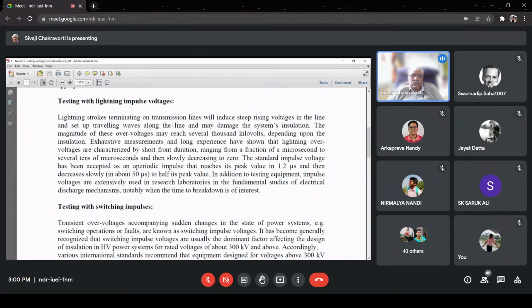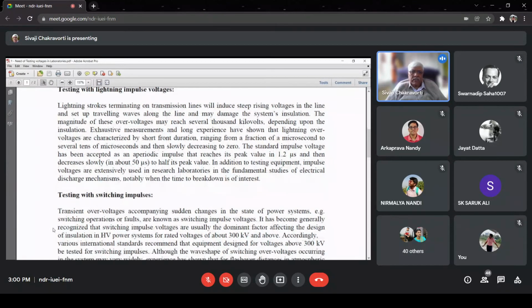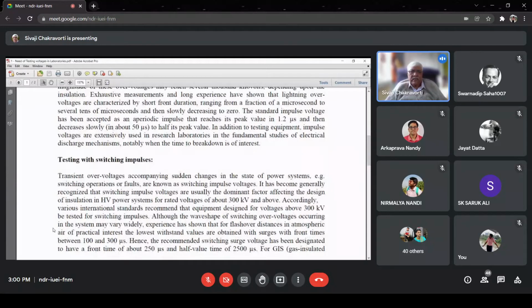So the moment we switch these equipments, there will be switching impulse, because from your circuit theory knowledge, you must be knowing that the moment a circuit topology changes, topology means that any component is changed, any circuit configuration is changed. This is called change in topology of the circuit. So anytime the circuit topology changes, there will be a transience, which can be analyzed by Laplace transform and others. So we can find out such switching impulses, and they will be there in the system, and they are also higher voltages. So we need to generate switching impulses also in our laboratory.